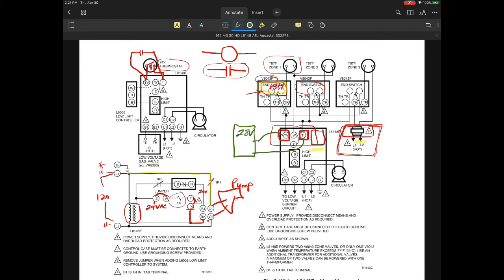So, a couple of takeaways from this. One of them that I hope you have taken away is that on all of these systems, really, the Aquastat is a temperature limiting device. The Aquastat generally can have relays built in that will also control the circulator in addition to the burner circuit. When you have zone valves, typically you'll have thermostats that will power up the individual zone valves, and then you will take isolated sets of contacts to complete the thermostat demand.